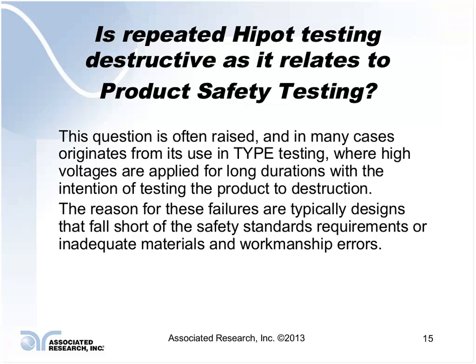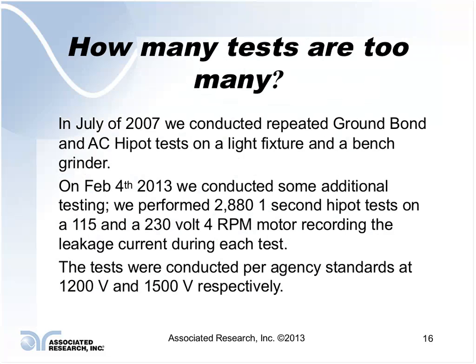And I think that's the question that we're trying to answer in this webinar. Is that type of testing destructive? Do I have to worry about it? And if your product is manufactured in accordance to the specified standards, you're using insulation, creepage, and clearance distances that are recommended, I don't think you're going to run into a problem.